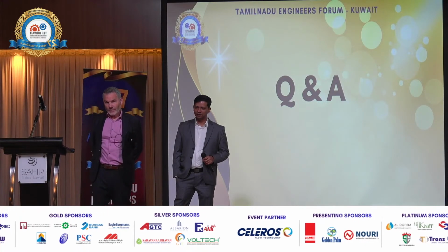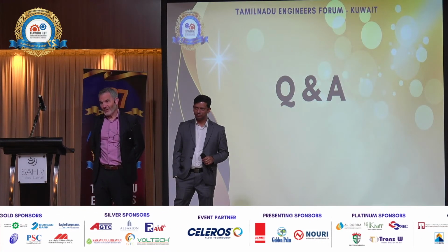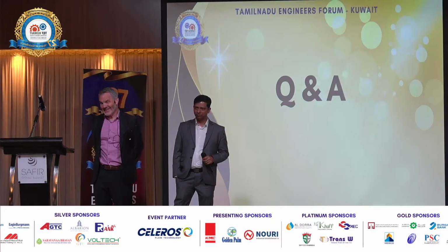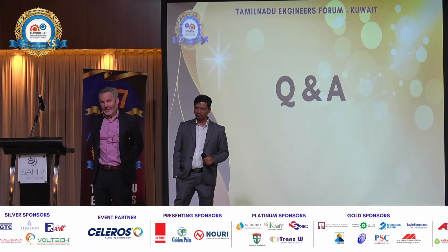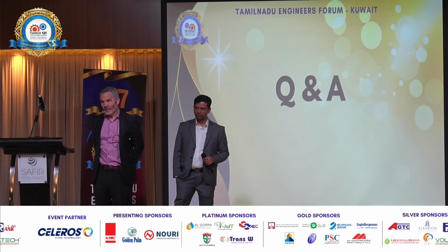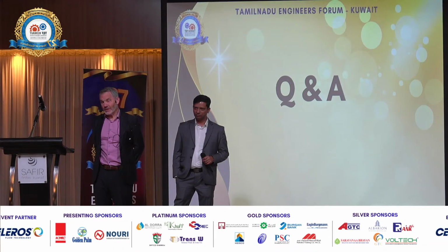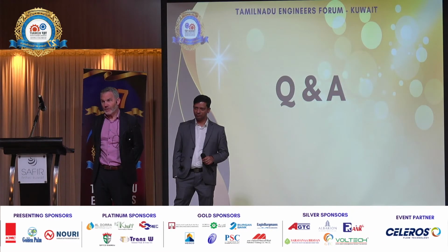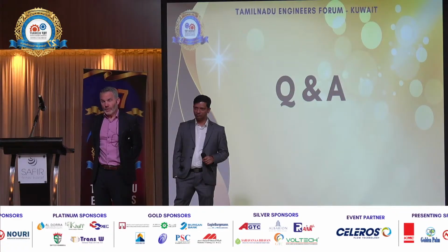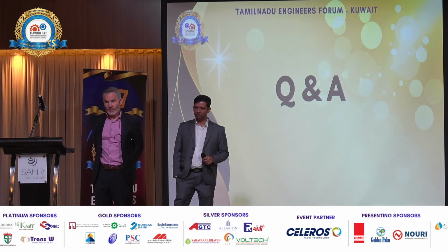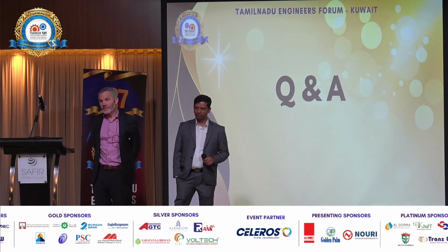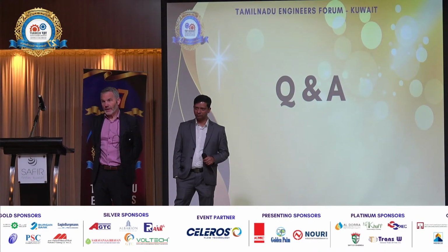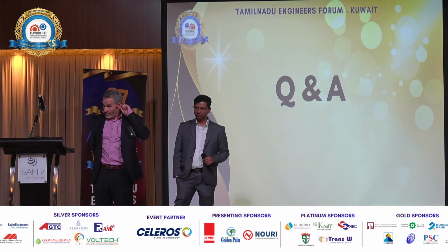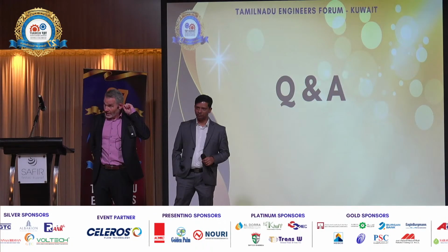Yeah. I mean, there are some pump manufacturers out there that recommend that the end user overhauls the pump every 2 years. And these are big pumps, big seawater cooling pumps, but we're telling the end user, you should be getting about 6, 7, 8 years out of these pumps before you overhaul them.